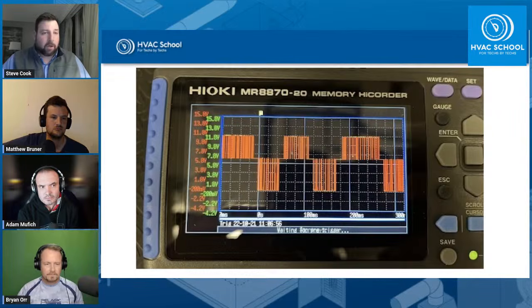If you do have a fault code, that makes it easy, because with communicating systems everything's addressed, so they'll tell you where the fault is. Say you have a daisy chain system with a communication fault on indoor unit number 5, and you can't see units 6 through 10 - out of 10 indoor units you only see 5. That gives you a good indication of where to look.